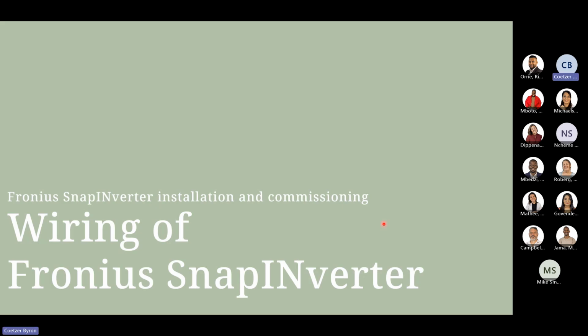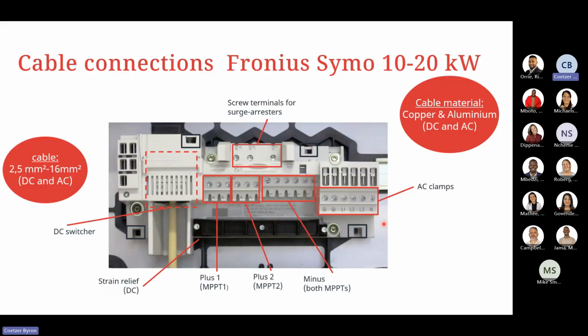So next is the wiring of the Fronius Snap inverter. It follows the same basic concept as the Gen 24, apart from us not having Wago disconnect quick clamps for the DC and AC side, but we have physical termination points that we need to fasten into the unit. What you'll notice again on the left-hand side is where your DC connection points are located, and on the far right-hand side is your AC clamps.